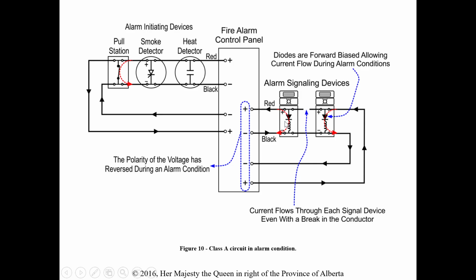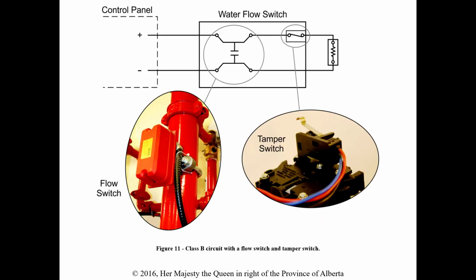Again, now these are forward biased, and this is working. They even show that there's a break here, but each device is still working. Again, that's because it's backfed from the panel here, so this device will continue to work even though there's a break here. That's the huge advantage between A and B. B has end-of-line resistors, A does not; it loops back to the panel. A has the huge advantage that if we have a break, our devices still work and remain operational, which is obviously great for safety concerns.